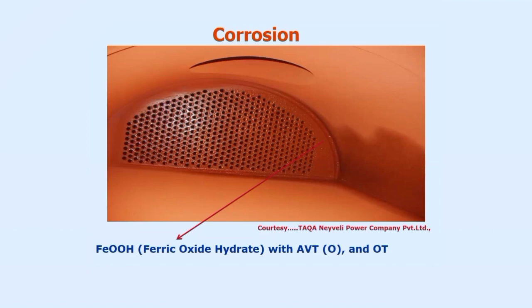In AVT(R) treatment, we are not using TSP in the drum, but we are using ammonia and hydrazine dosing after deaerator treatment. Now, what is the difference between this treatment and AVT(O) and OT? In AVT(O) and OT treatment, we do not use hydrazine at any point of time. In AVT(O), we are using only ammonia and nothing else. In oxygenation treatment, we are using ammonia and oxygen dosed at certain points.